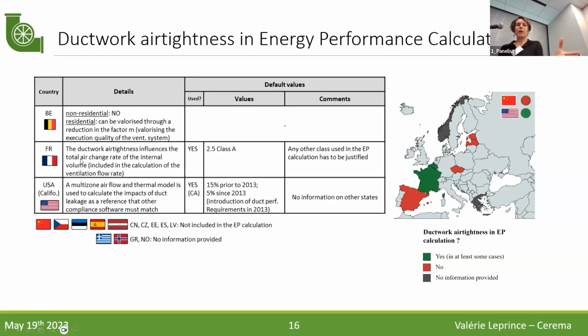For example, in the French case, we don't implement the impact on fan power of the ductwork airtightness test. This means if the ductwork is leaky, technically the fan will have to run faster to compensate for the leakage, but this isn't taken into account in the calculation—only heat losses are.